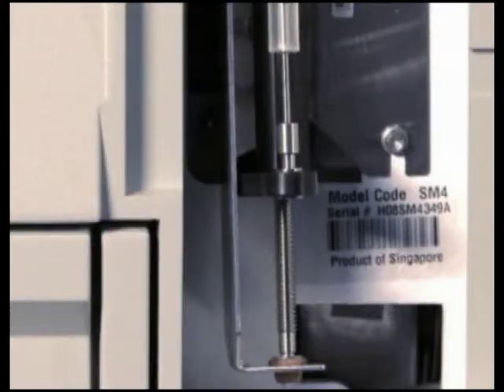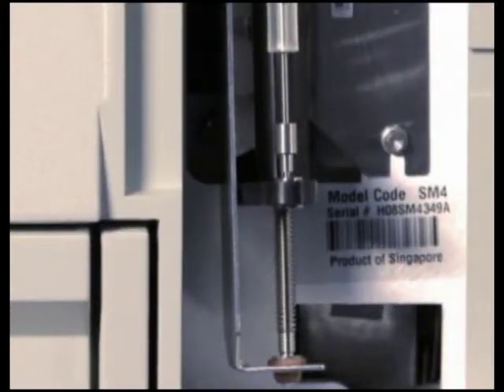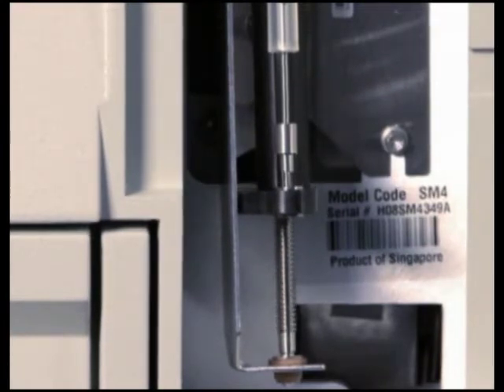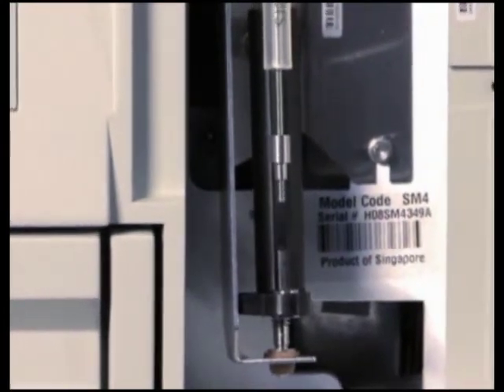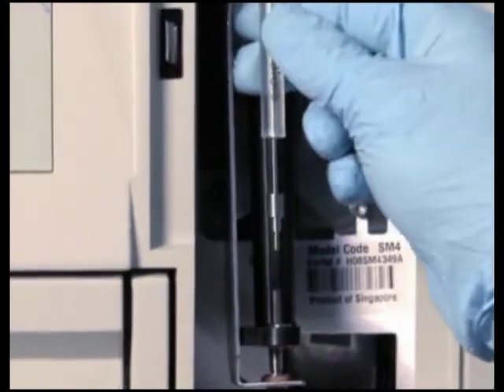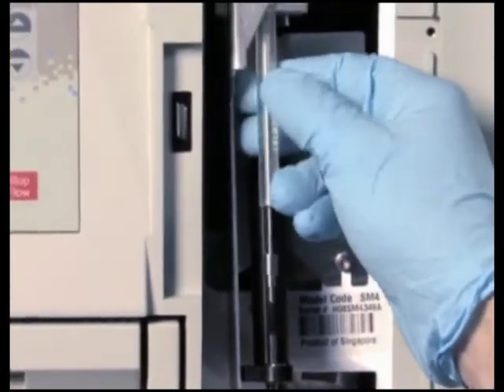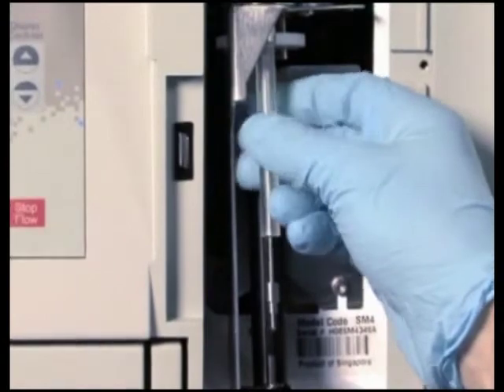With the knurled nut removed, the plunger tip remains pointed upward as the mounting bracket is lowered. When the mounting bracket is fully lowered, unscrew the syringe from the syringe drive mounting block and remove the syringe from the compartment.